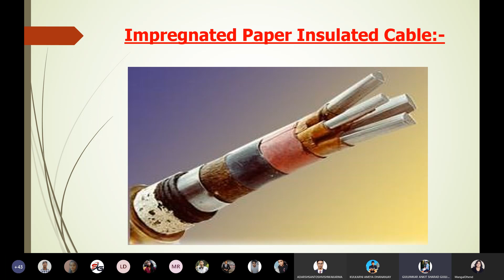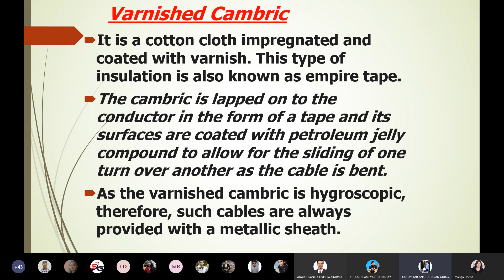The next is varnished cambric. It is cotton cloth impregnated and coated with varnish. This type of insulation is also known as empire tape. The cambric is lapped onto the conductor in the form of tape, and its surfaces are coated with petroleum jelly compound to allow for the sliding of one turn over another as the cable is bent. As the varnished cambric is hygroscopic, such cables are always provided with a metallic sheath.